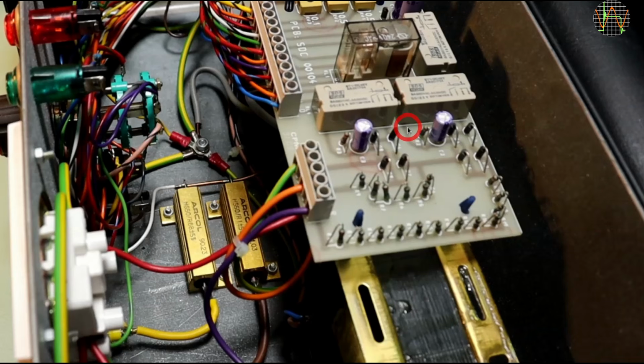Instead of having to transform low voltage drops to drive a relay, we now have the problem of way too much voltage. So the circuit consists of lots of resistors in series to drop the voltage for the relays, which are the 48 volt types. There is the usual rectification and smoothing cap for each circuit. This area is for class 1 because it has far fewer resistors as it deals with less voltage. So obviously the logic is the other way around from the earth resistance test. If there is sufficient high voltage to operate the relay, the insulation is okay. If the voltage collapses because of bad insulation, the relay will not operate and the device and the test fails.